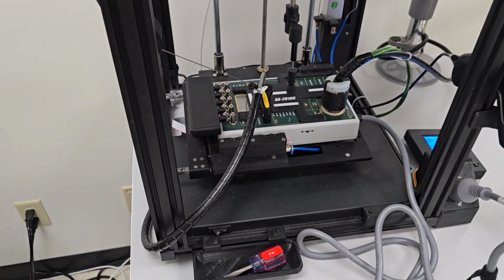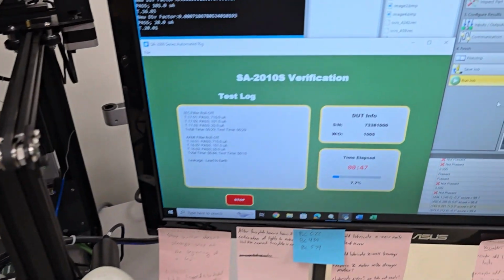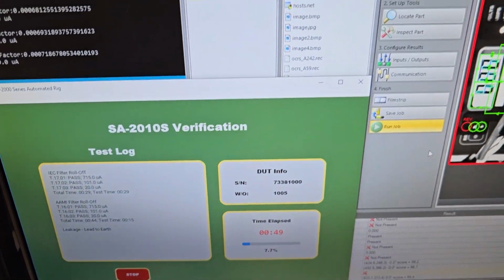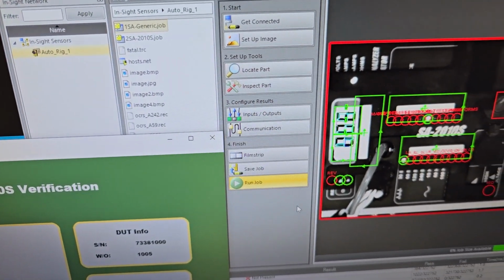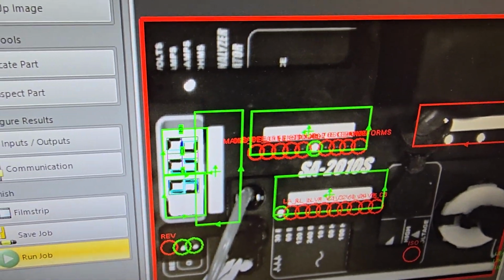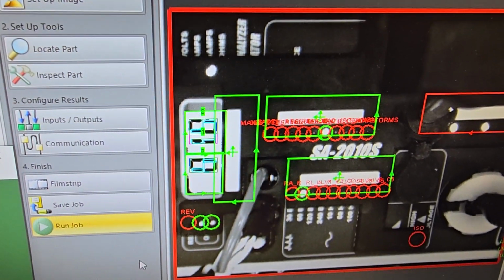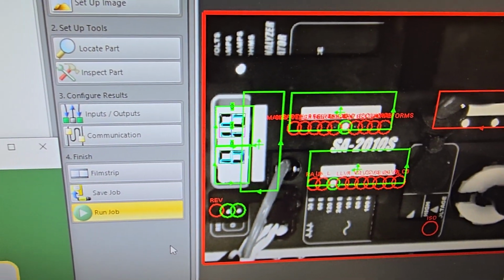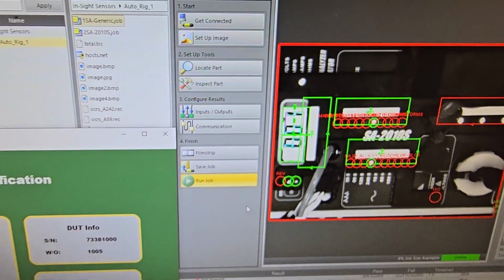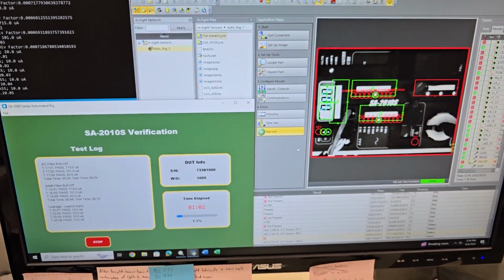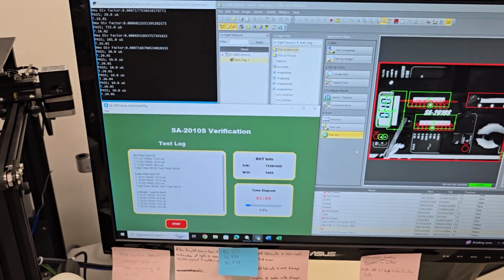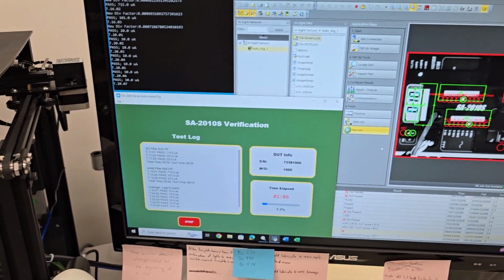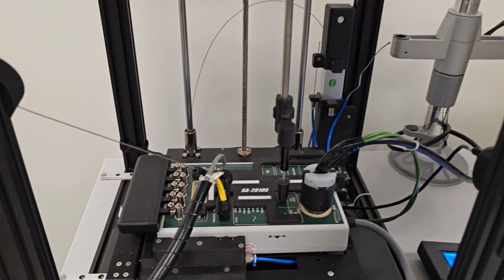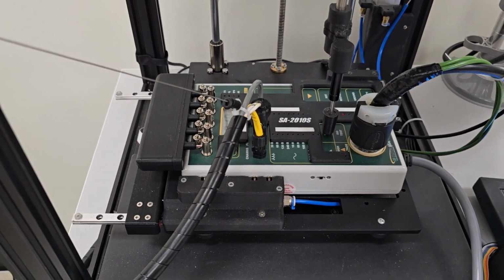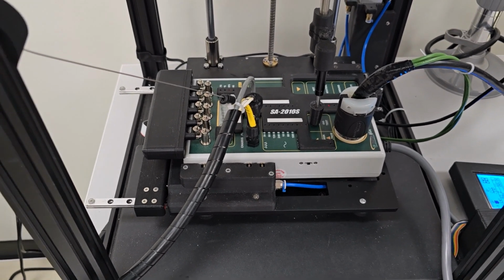We can see here that it's detecting the readings of the unit. That's the optical character recognition for all of the indicators. Look at that. You're right. So it verifies that the correct mode is active. So even a device like the safety analyzer that doesn't have an RS-232 or Bluetooth, we can still automate that process. Yeah, because light is the only way that you'd communicate what mode it's in. Right. We read the LEDs. That's so cool.